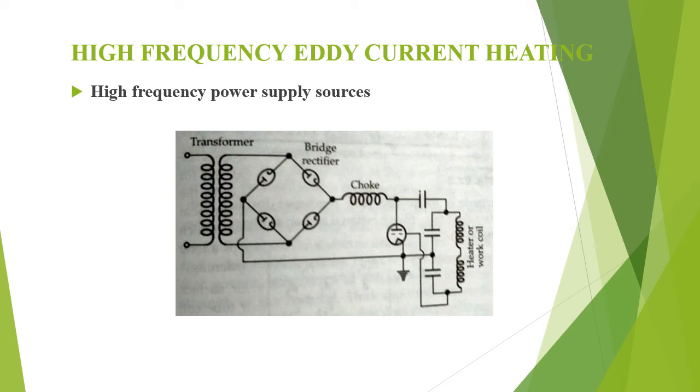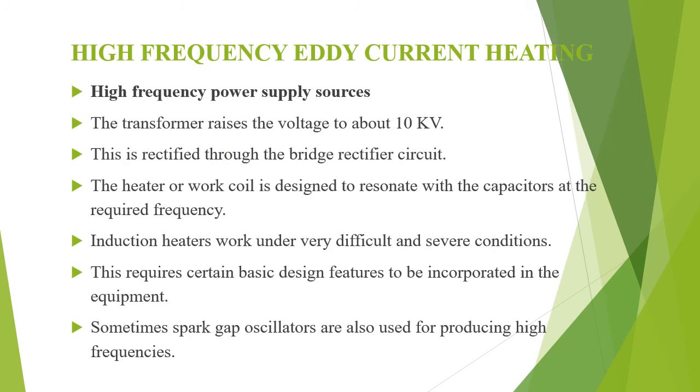But the induction heaters work under very difficult and severe conditions. This requires certain basic design features which have to be incorporated in the equipment. All the protective devices should be designed for heavy duty service, since the heater has to work under widely varying load and sometimes even under short circuit conditions. The clearance for high voltage is longer from the safety point of view. Other components should be made as robust as possible. All controls are made for heavy duty and the equipment should be able to withstand movement from one place to another in the shop.